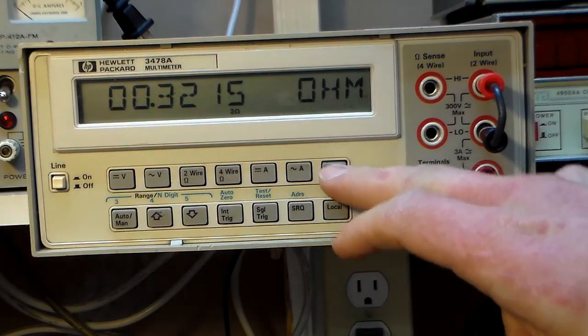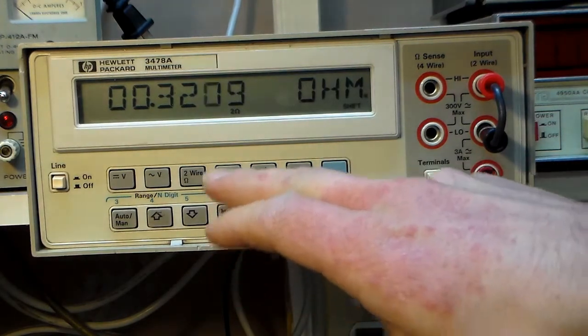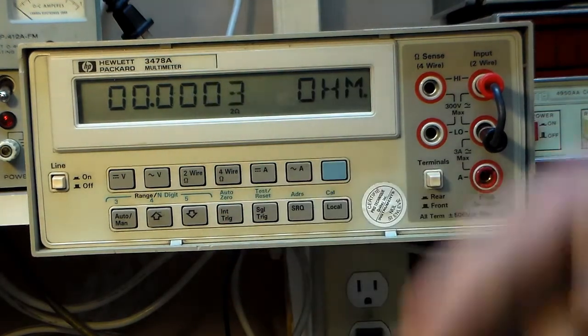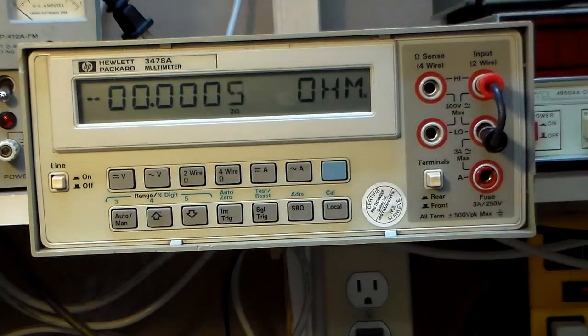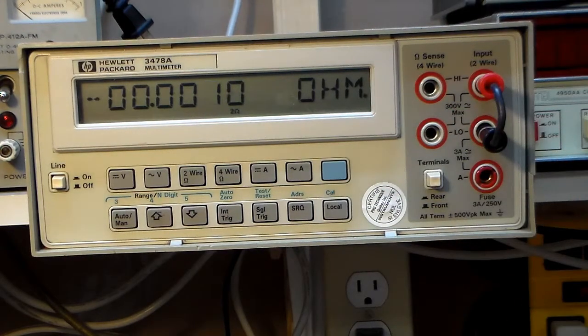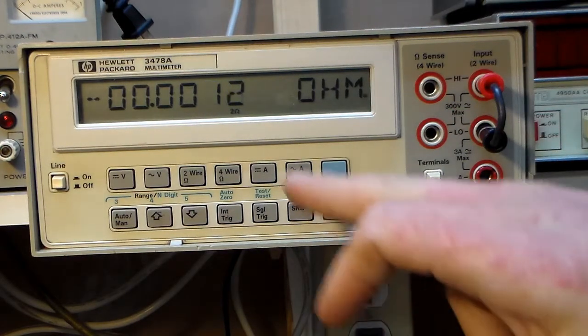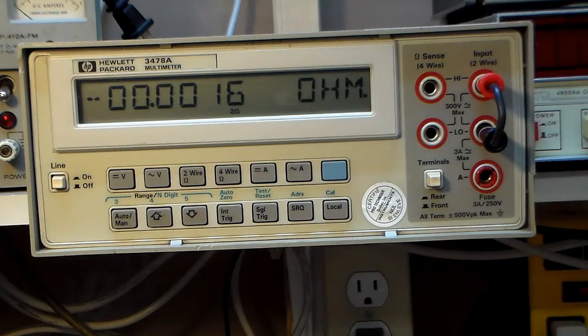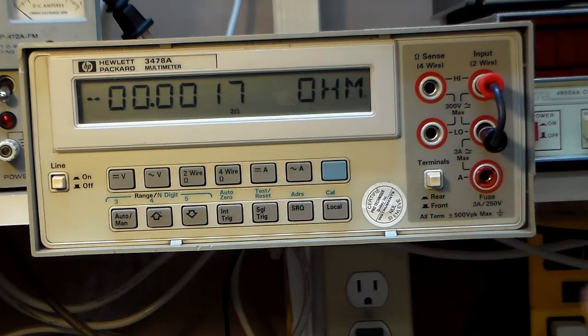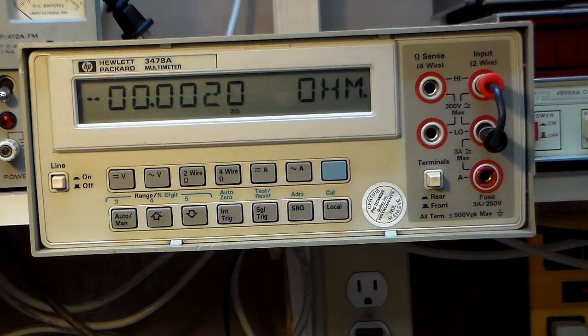But with the relative mode, I activate it with Shift 4 like this. It saves the current reading and subtracts it from all the next readings. So here we're just seeing it drift because I just turned it on and it's just warming up.